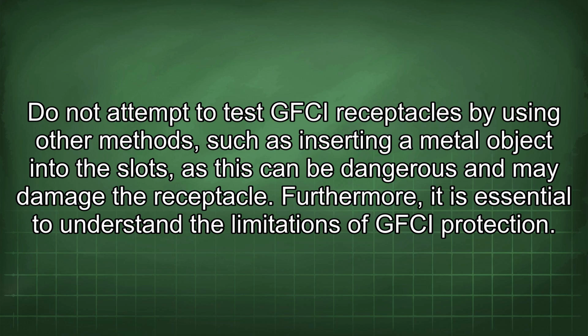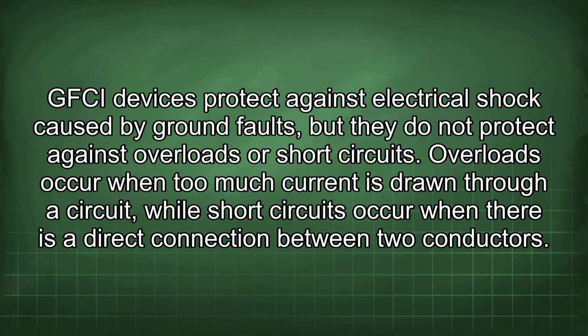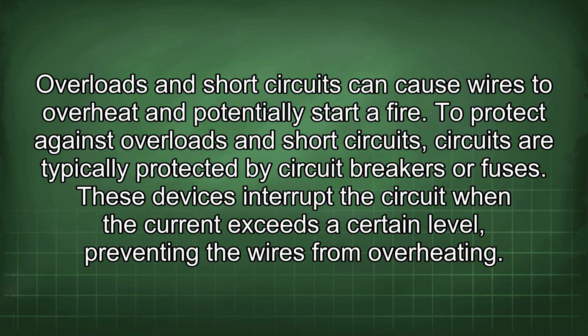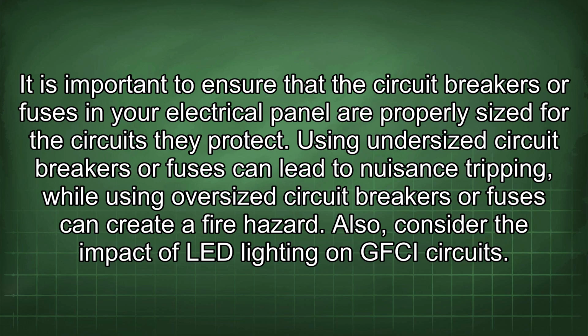Furthermore, it is essential to understand the limitations of GFCI protection. GFCI devices protect against electrical shock caused by ground faults, but they do not protect against overloads or short circuits. Overloads occur when too much current is drawn through a circuit, while short circuits occur when there is a direct connection between two conductors. Overloads and short circuits can cause wires to overheat and potentially start a fire. To protect against overloads and short circuits, circuits are typically protected by circuit breakers or fuses. These devices interrupt the circuit when the current exceeds a certain level, preventing the wires from overheating. It is important to ensure that the circuit breakers or fuses in your electrical panel are properly sized for the circuits they protect. Using undersized circuit breakers or fuses can lead to nuisance tripping, while using oversized circuit breakers or fuses can create a fire hazard.